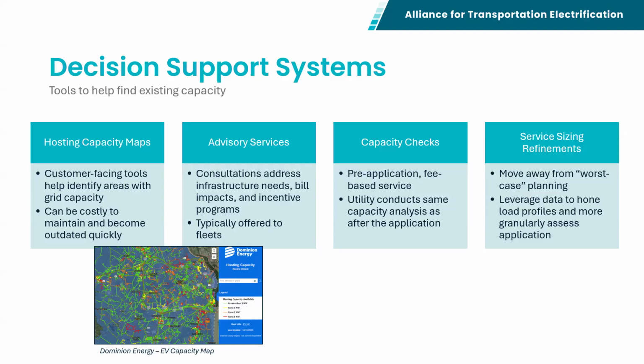Then there's also service sizing refinements. Historically, utilities have had a worst-case planning approach. So if somebody brings a site onto the grid with, say, 4 megawatts worth of EV charging behind that meter, the utility assumes they're going to use all 4 megawatts at a single time—which may or may not be true—and that they'll use all 4 megawatts during the 15 minutes or the hour that the grid is most constrained in that area, which also may not be true. So using data and existing systems, utilities increasingly are honing their load profiles and assumptions about how incoming load will fit with existing load on the system.